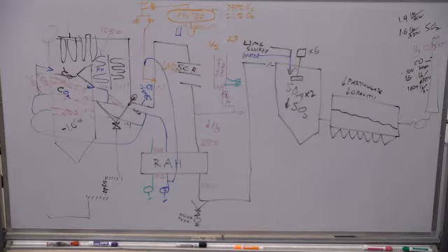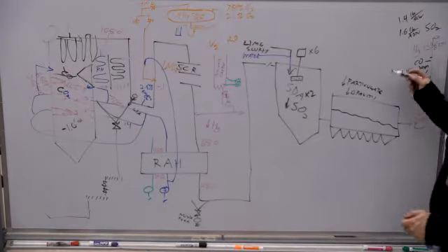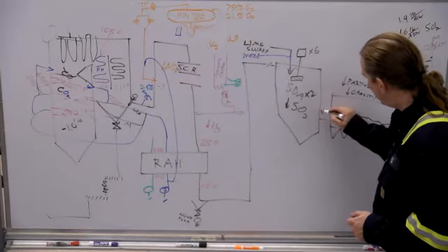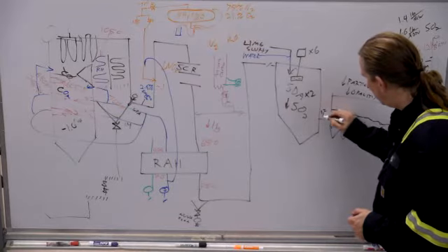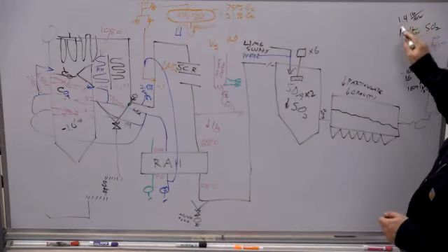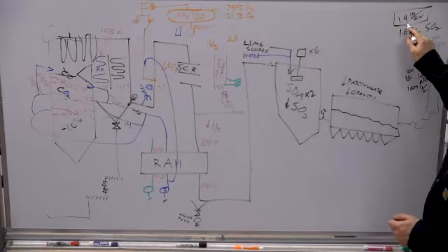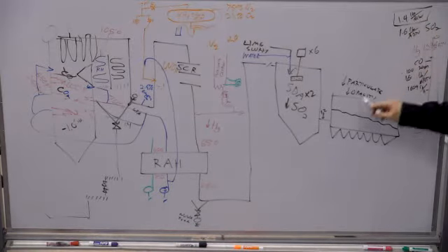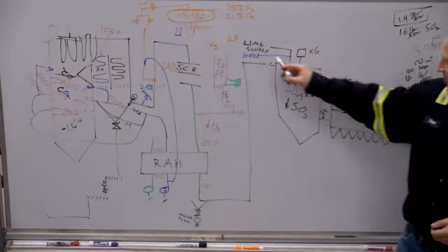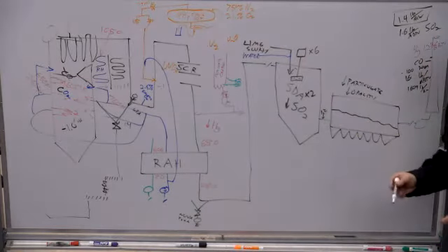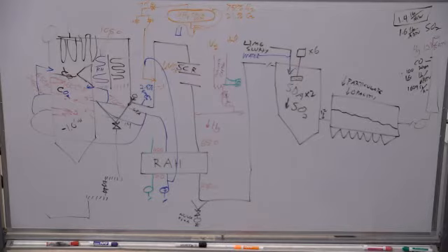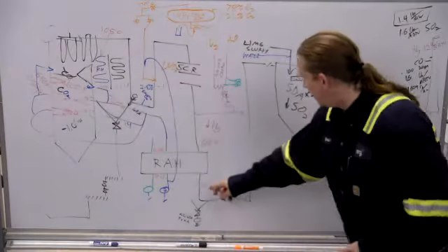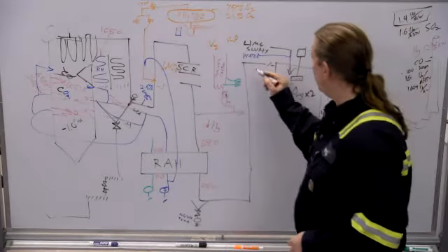So we picked 1.2. This 1.4 pounds per megawatt, the pounds per megawatt is what we're actually controlling for, and 1.2 is what the lime slurry flow is shooting for. So we said we're 280 there. We're still 280 going in.